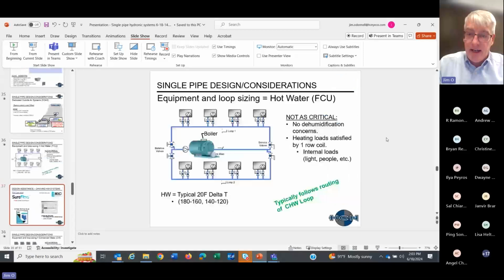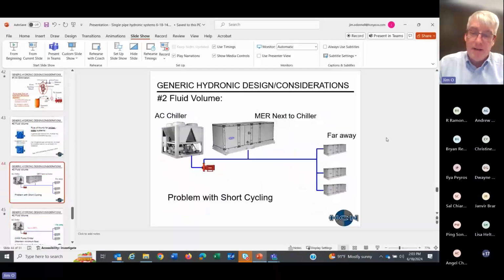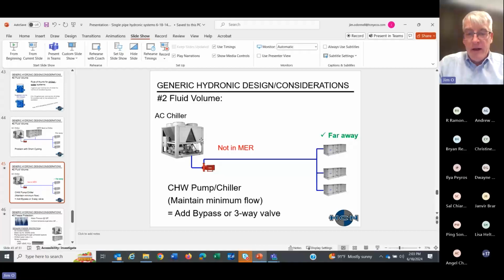Okay, the next question is, can you please explain again why we need a bypass for the chiller? I will apologize that this is a very poor diagram to explain that. With your chillers, you have a heat exchanger in them. So you'll size your chiller, say for 100 tons. A normal flow is 2.4 GPM per ton, so at full capacity you have 240 GPM going to that chiller.